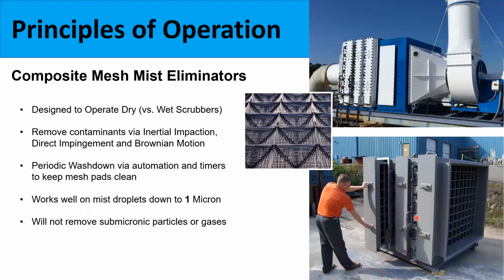Again, just like the vertical unit, the scrubber is provided with an entrainment separator, whether it's in the form of packing, chevrons, or mesh pad assembly, again, to capture the entrained liquid droplets in the gas stream prior to discharging from the unit.